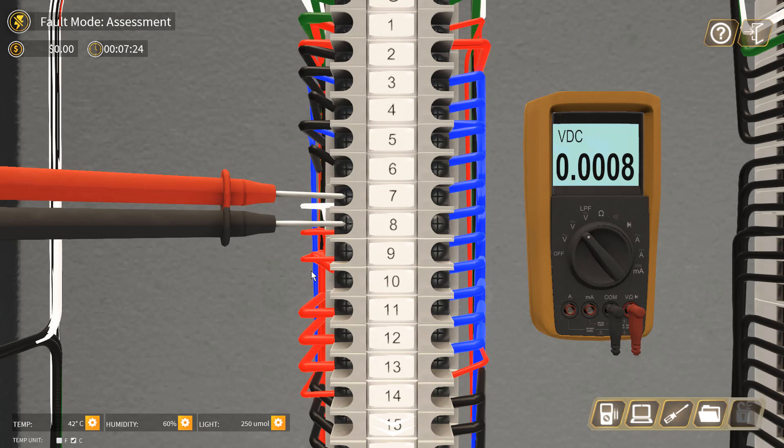Most likely either the card is having an issue or the RTD is having an internal short circuit. So we can do the isolation check, check one by one. We check the RTD first, then we will check the PLC RTD module input.